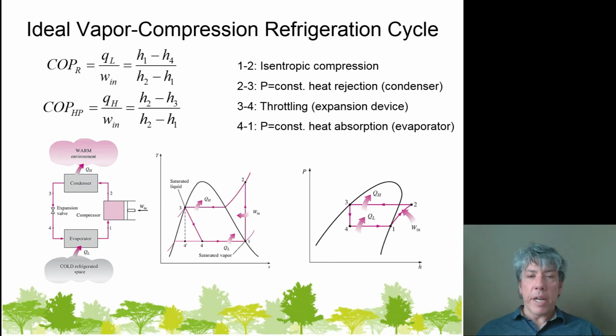So 70-degree air in the home can easily give up thermal energy to this refrigerant in a heat exchanger that's inside of your ductwork. And so if you've ever seen an A coil, for example, that's how it works. That's the evaporator. And its job is to absorb thermal energy from the surrounding air, put it into the refrigerant, and in the process boil off that refrigerant. So there's always a sort of a gas check so that liquid remains in the evaporator and only gas is allowed to escape the evaporator, because if there's still some liquid, that liquid still has a significant potential for being boiled off and for refrigeration.